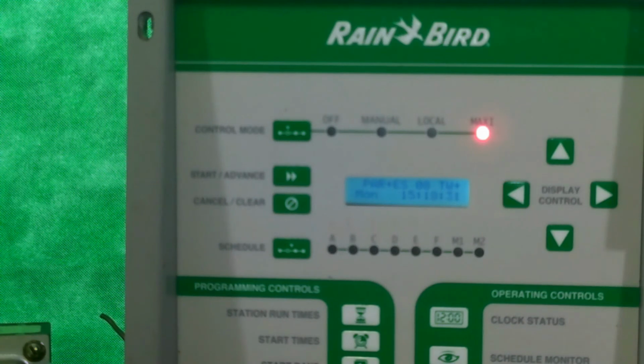The other thing we need to be aware of is if this module is working correctly, then if you look at the clock panel, in this case it's a Par Plus ES, you'll notice we have a display, but more importantly, you'll notice that there's a bright red LED that is sitting solid. And that means we're locked in to communicate and it will work. If for some reason that light is not locked on, and the voltage is correct, then there's a problem. And if that's the case, you need to take that 2-wire module and replace it with a working 2-wire module, and then you have that repaired.